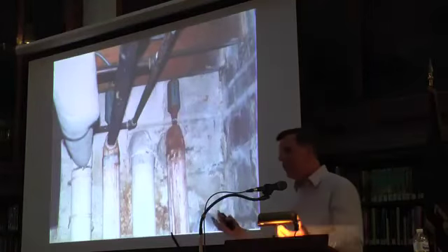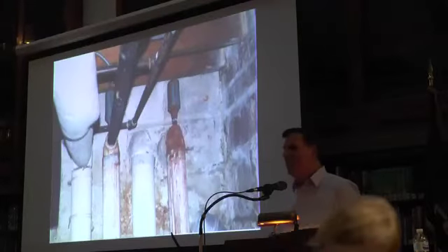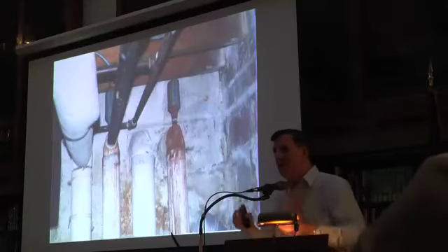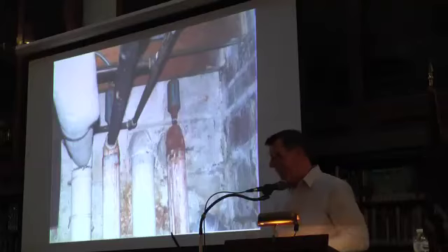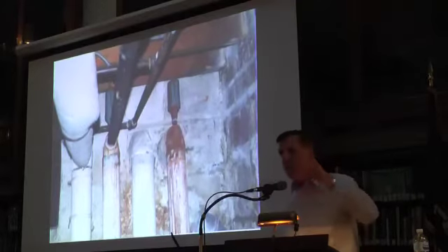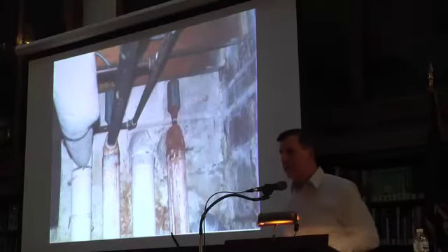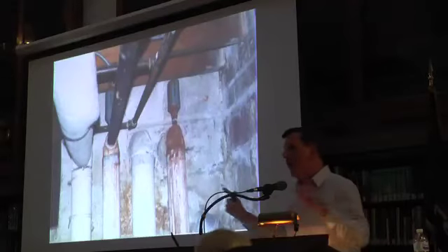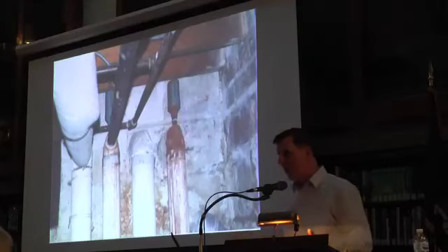When you raise the steam pressure, not only does the steam go slower, but also it compresses the air that can't get out, which causes you to raise the pressure even higher. See, it feeds on itself. So, knowing that the air vent is plugged up here tells me why there's no heat in the rest of the building. So with steam, I learned at an early age that the problem and the cause of the problem are rarely in the same place. You got to get out and be nosy. You got to wander around.